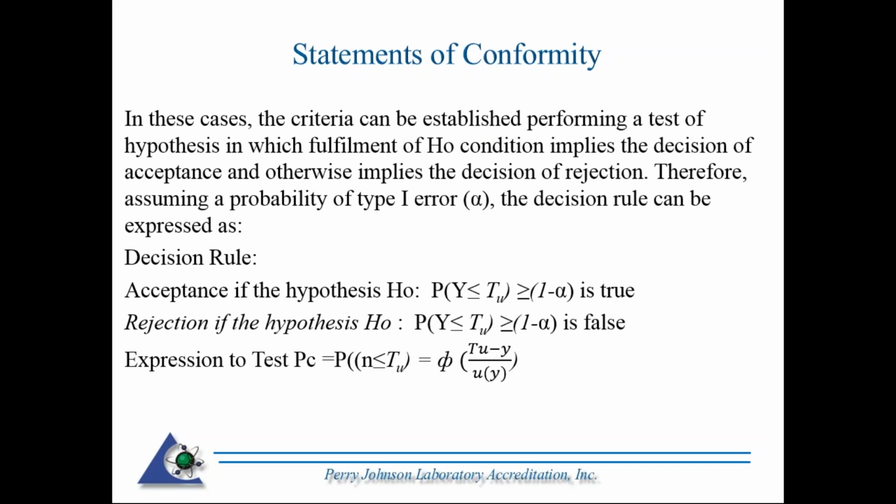So basically, what we're looking at here is, of course, the value being less than the tolerance limit. Now we have a function based on a Gaussian probability distribution function. And I'll go over this later on in the presentation, exactly what this is. But basically, it takes into account the calculation of the tolerance limit minus the actual recorded value and the actual measurement uncertainty.